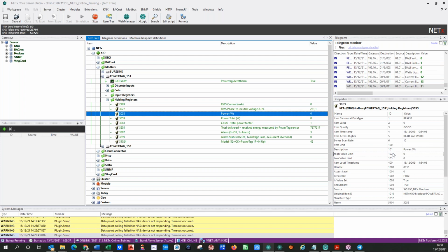So it should start consuming something now, and we will see the value if it's higher than we expect. No, it's okay. It's in watts. It's perfect. It should trigger the alarm. Now it's going down again, but it will increase. It's an inverter, so it's modulating the consumption.